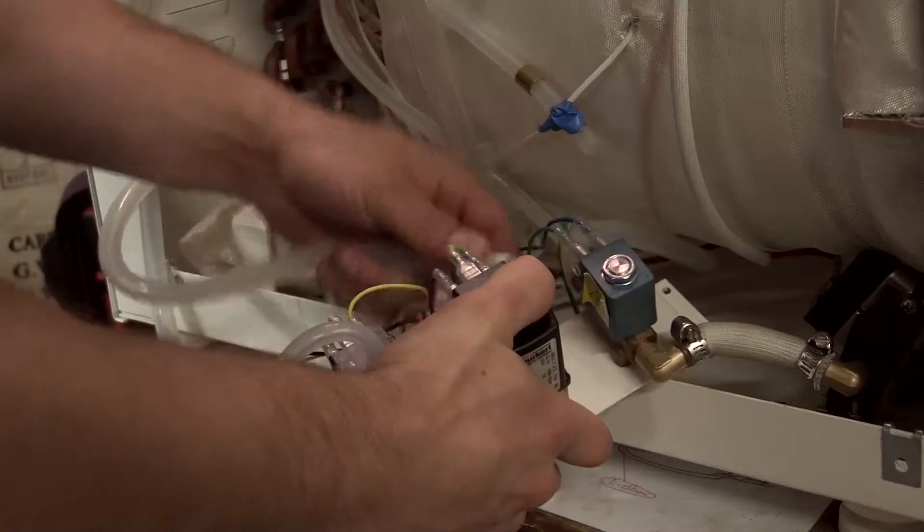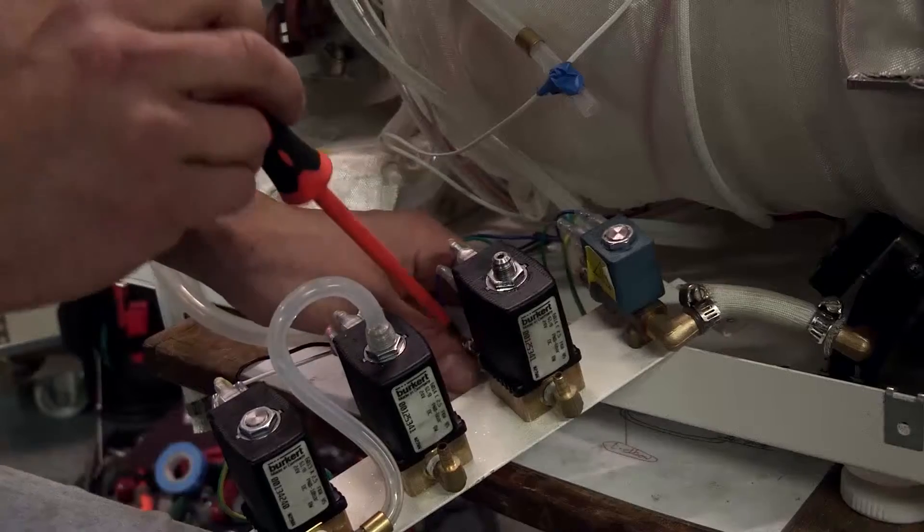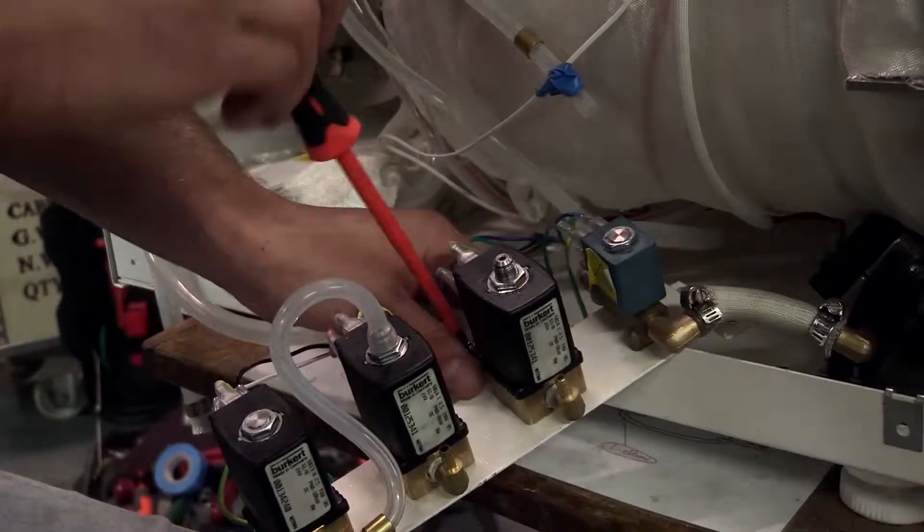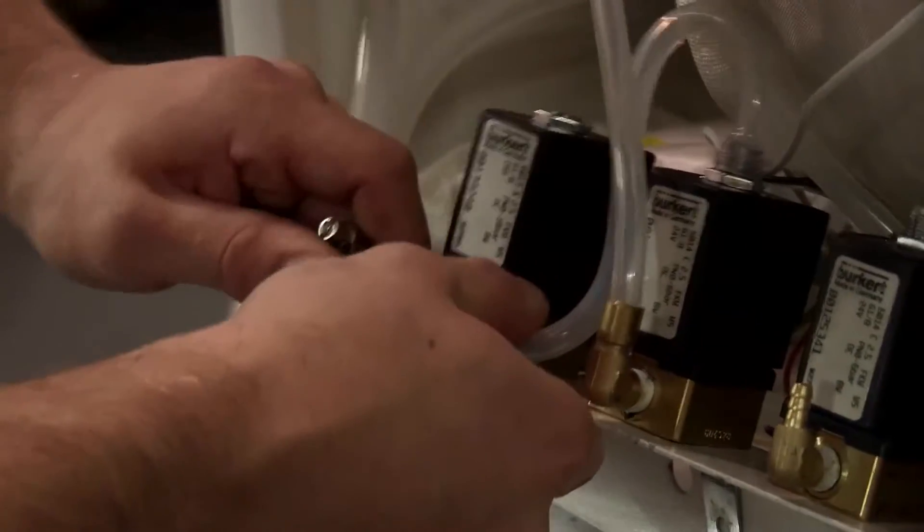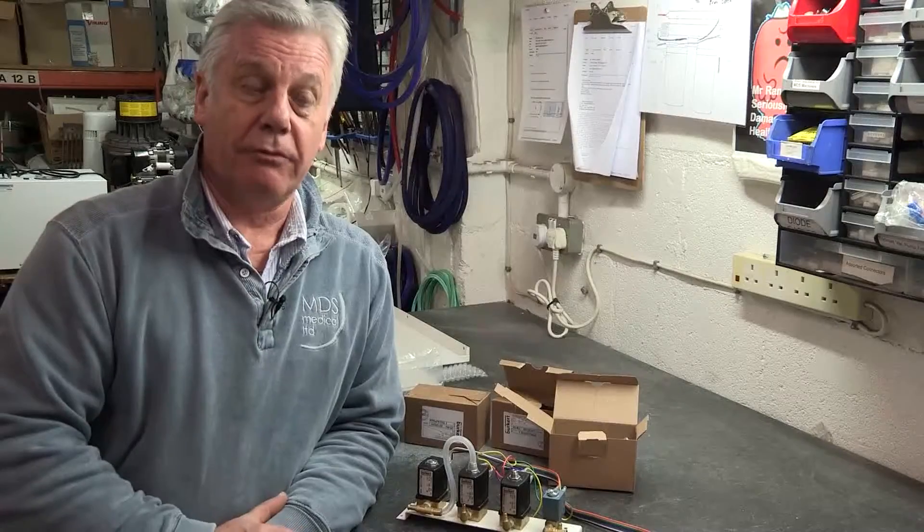We're finding that the duty that dentists use these machines, they could be running these machines 15 times a day, six days a week. That's a lot of duty for a small valve to be working. They work like a piano. It will open for a period of time and it will close for a period of time. So they're constantly in use through the cycle.